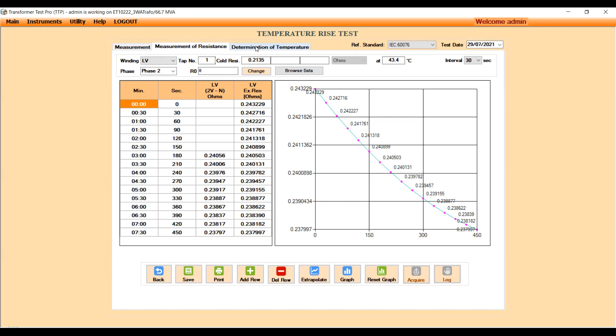Next is determination of temperature. Once you come here, you'll be in a position to get the results. Results are very simple for the HV winding, the LV winding, the tertiary winding, all the information. In the bottom, the last two rows you see are the results: top oil temperature rise and the winding temperature rise. You'll be in a position to see it here.